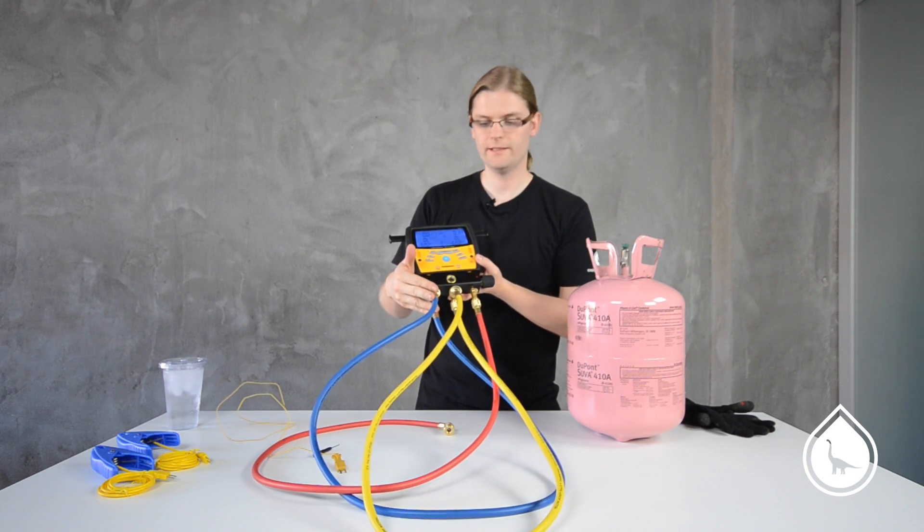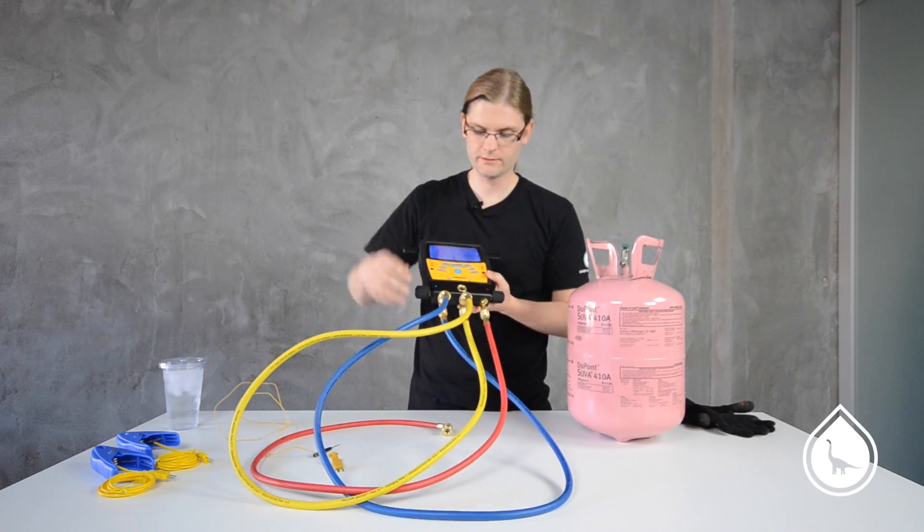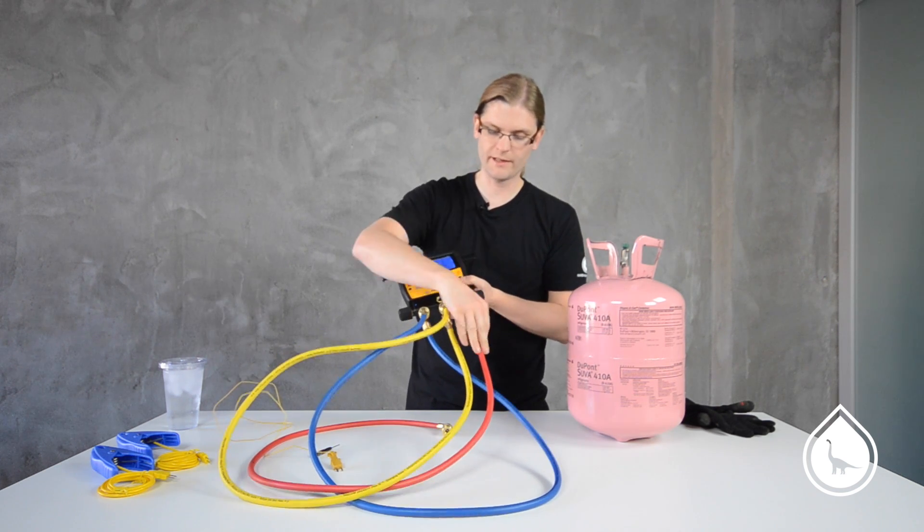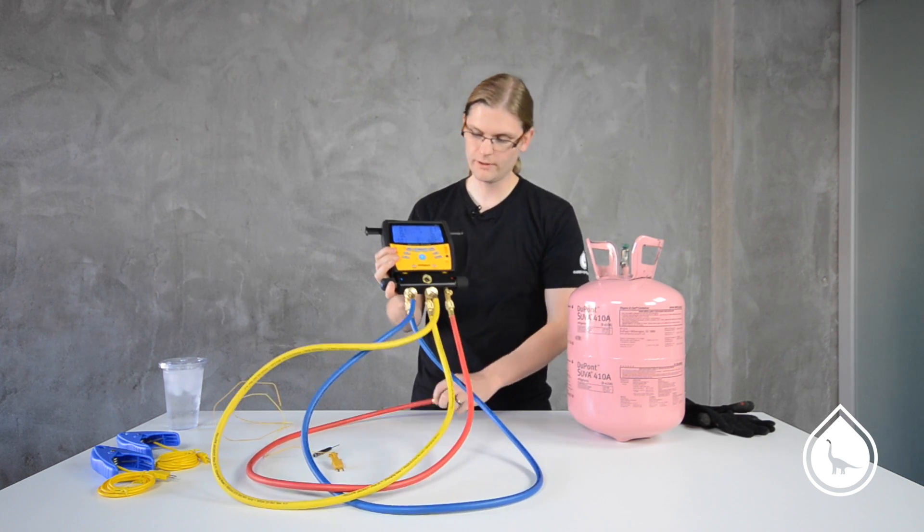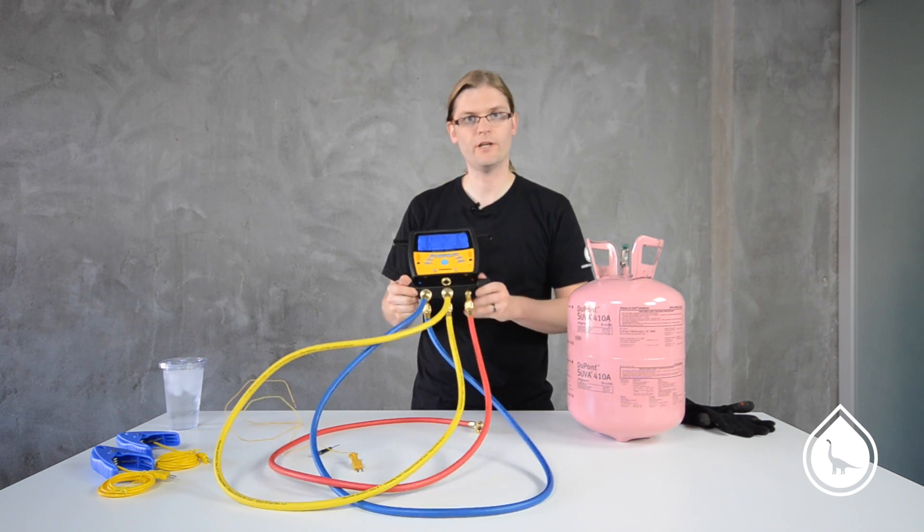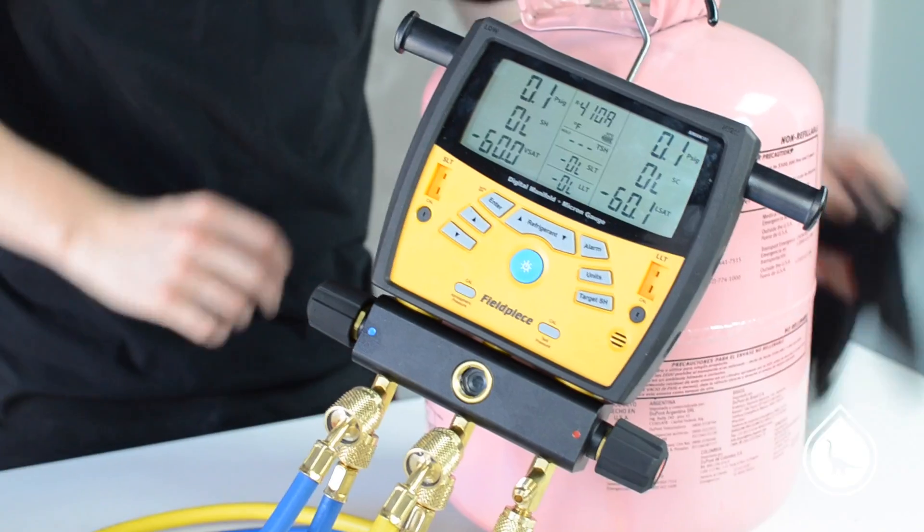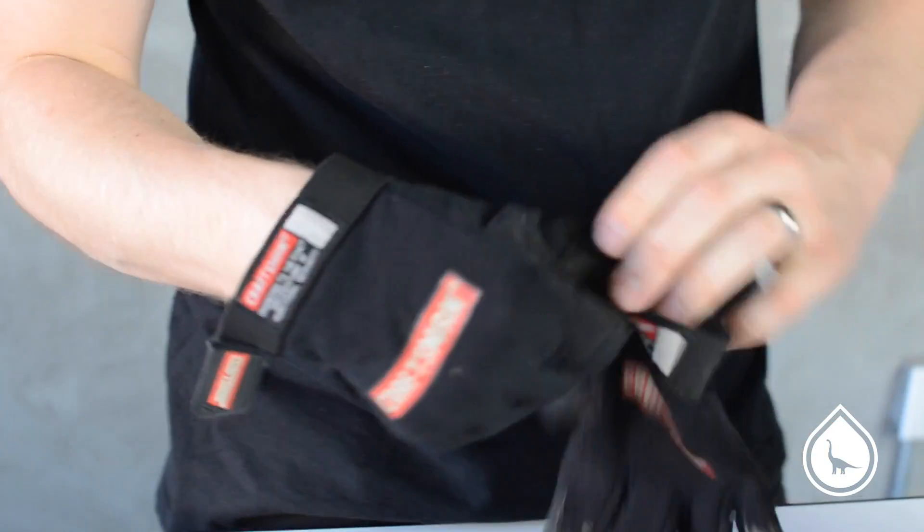I've got my low side connected, top bottom, so it's returning to the manifold. I've got my filling line connected the same way, and I've got my high side with one end on, other end open, going to be connected to our tank. I've also got the manifold open completely so that both pressures should be reading equal. I'll throw my gloves on and get this connected to the tank.